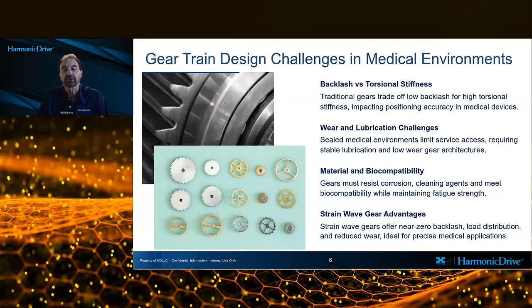Gear train design challenges in medical environments. Designing gear trains for medical applications involves navigating several competing requirements that are often in tension with one another. One of the most critical trade-offs is between backlash and torsional stiffness. Conventional gear technologies such as spur or planetary gears can achieve high stiffness, but typically at the cost of measurable backlash, which degrades positioning accuracy and force control.